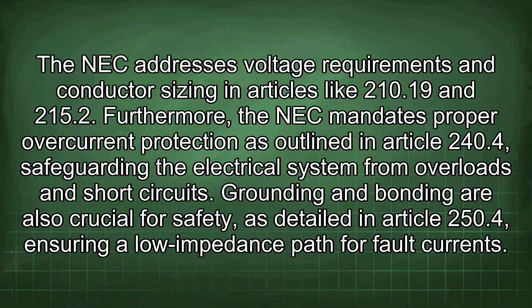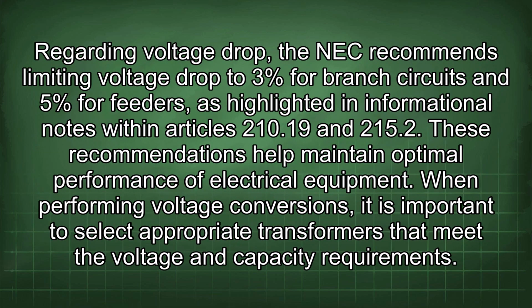The NEC addresses voltage requirements and conductor sizing in articles like 210.19 and 215.2. Furthermore, the NEC mandates proper overcurrent protection as outlined in Article 240.4, safeguarding the electrical system from overloads and short circuits. Grounding and bonding are also crucial for safety, as detailed in Article 250.4, ensuring a low impedance path for fault currents. Regarding voltage drop, the NEC recommends limiting voltage drop to 3% for branch circuits and 5% for feeders, as highlighted in the informational notes within Articles 210.19 and 215.2. These recommendations help maintain optimal performance of electrical equipment.